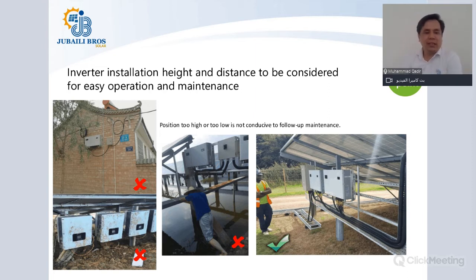Similarly, in the picture shown at the center, the solar inverters are installed in a floating PV plant, at a location where it is not easily accessible. Normally in such scenarios, it is good to have some walkways just beneath the solar inverter so that you can easily access it for maintenance purposes.